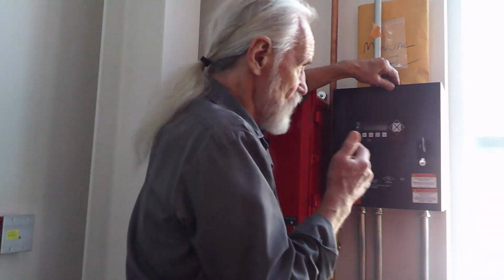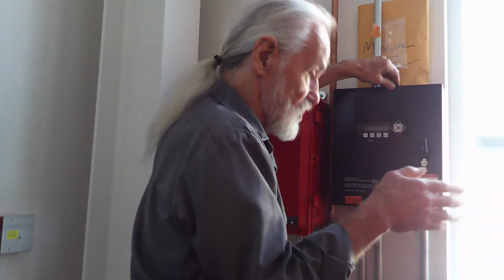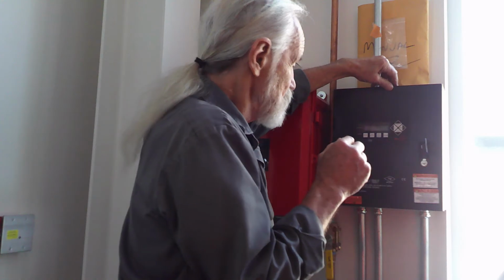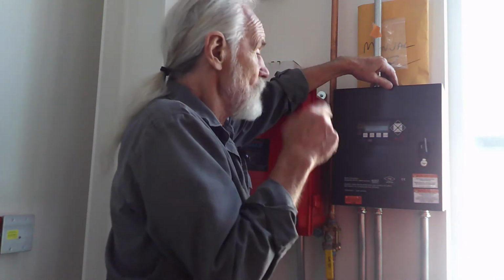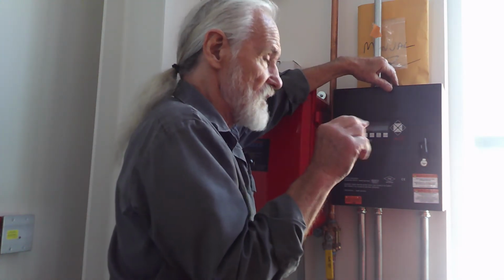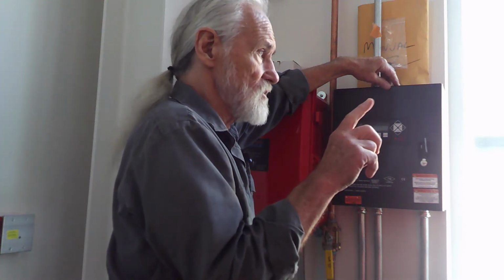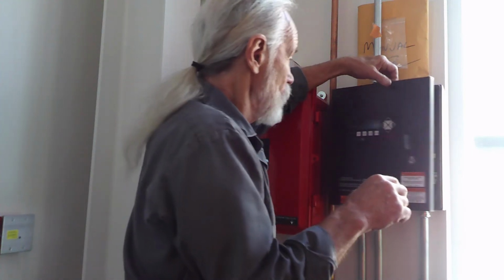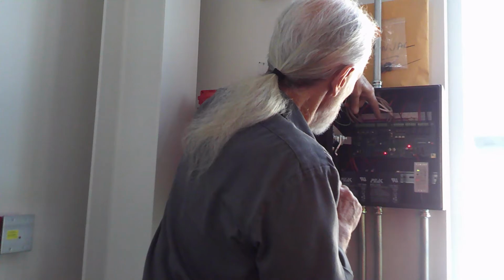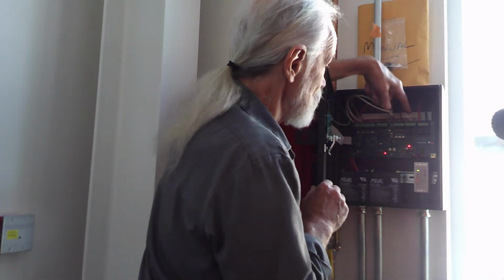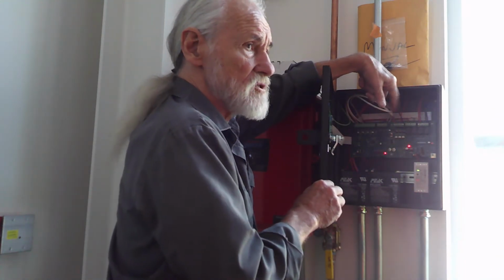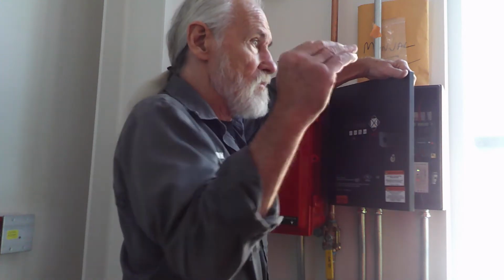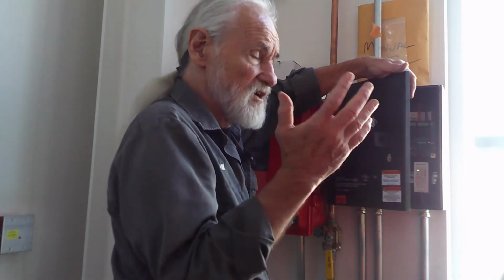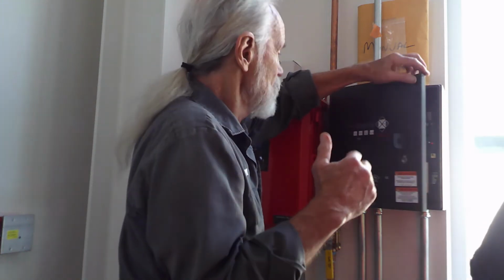The first one you check, I'll show you how. It checks the spark detector, and it'll do that in normal mode. That's the only one you can test. You can't fool with the rest of them. When it's in service, it actually throws these relays, so it doesn't do it instantly like it would if there was a fire.